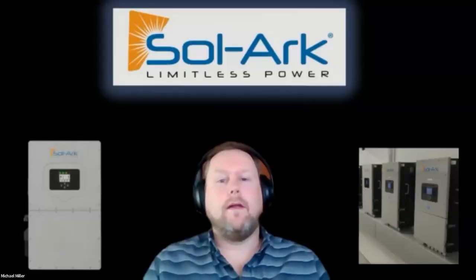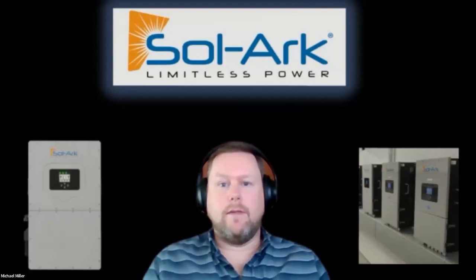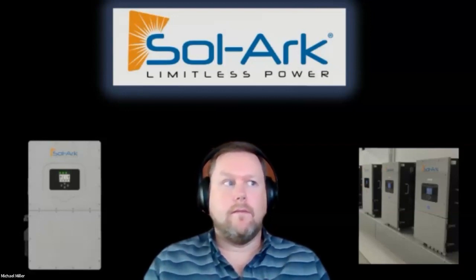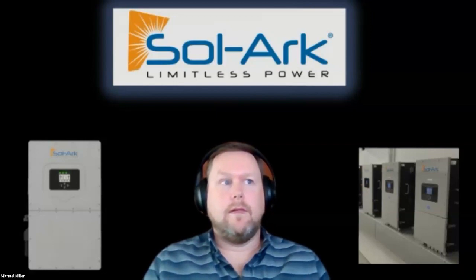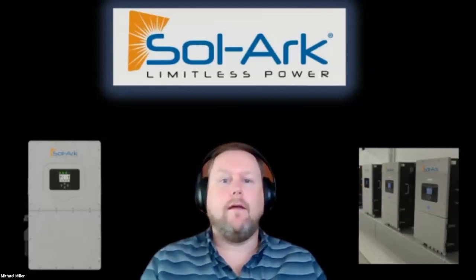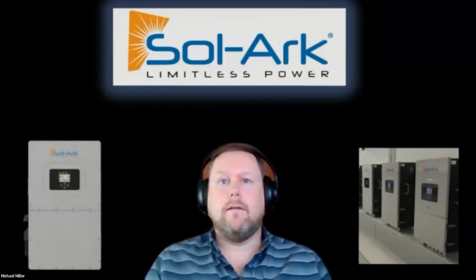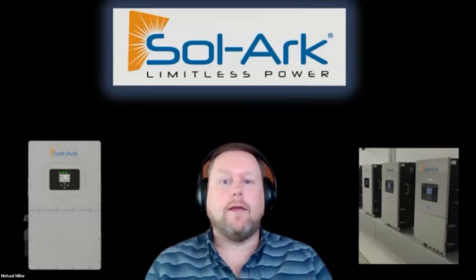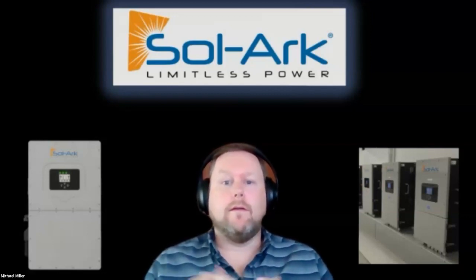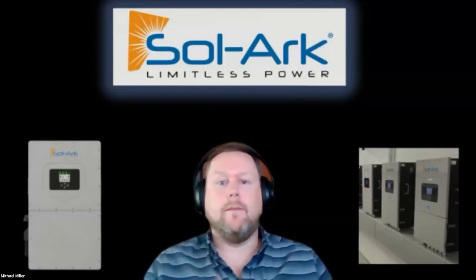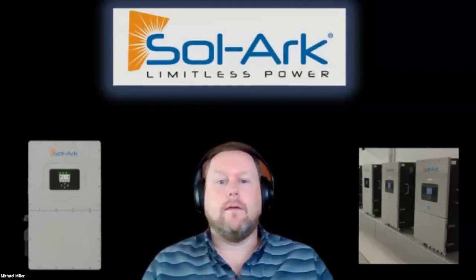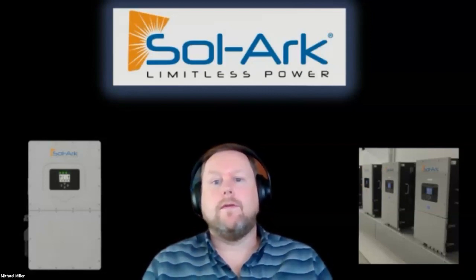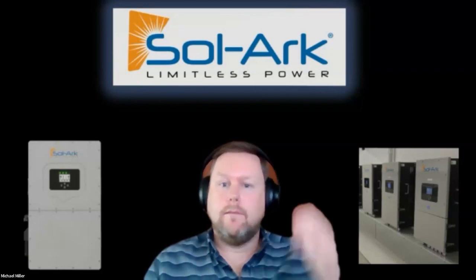In general, we have a charger built into the inverter, so it would be duplication. DC charge, I mean the solar panels are DC charging. If you're talking about export limits, installers can petition the utility to have a password-locked export limit. So then you could have the 15K but only be approved for say 8K. In a couple of utilities we've gotten them to accept that as a solution for limiting the selling ability of the inverter.